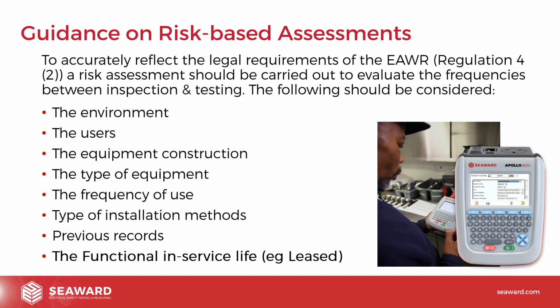Similar with IT equipment, you might have a maintenance or a leasing arrangement with your IT provider, and you know that every laptop is going to last 2 years and then it's going to be taken away, got rid of, and a new one's going to come in. So again, those sorts of things can be factored in when you are doing your risk assessment. But generally, the list is pretty much the same as before. And I always point out, although these are the ones that are in the Code of Practice, this is not an exhaustive list. There are lots of factors like the age of the equipment and things like that that you may want to factor in that aren't on this list. This is just the key points that are listed in the 5th edition now. And obviously they've added that new one in there at the bottom, the functional in-service life too.